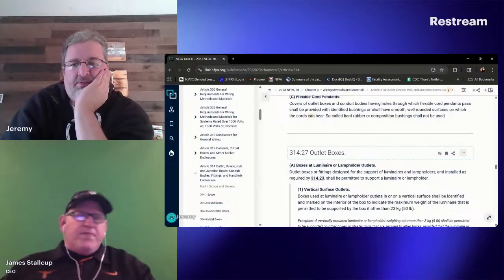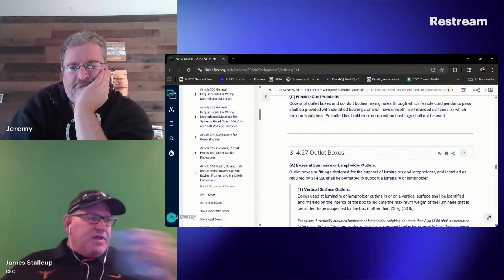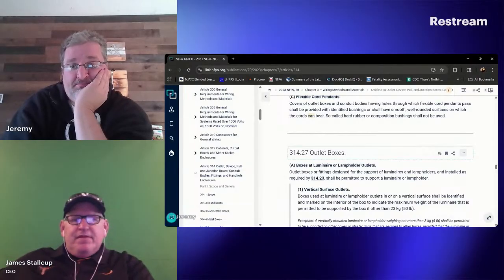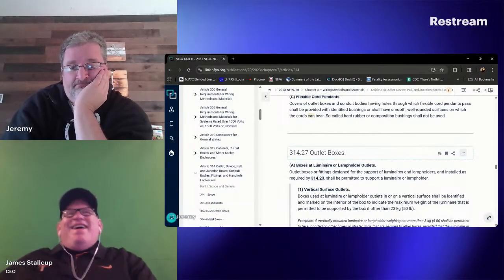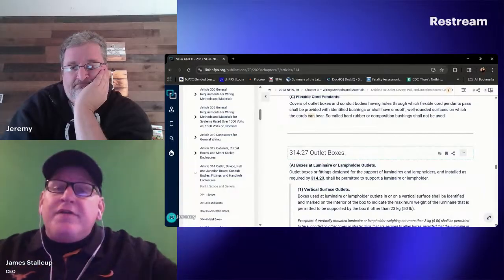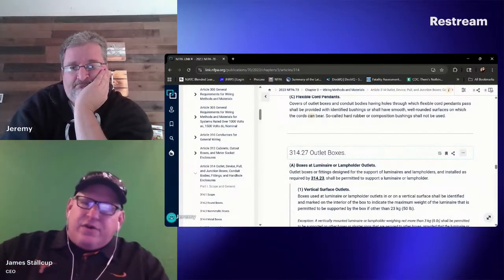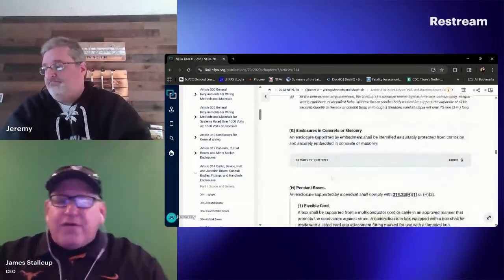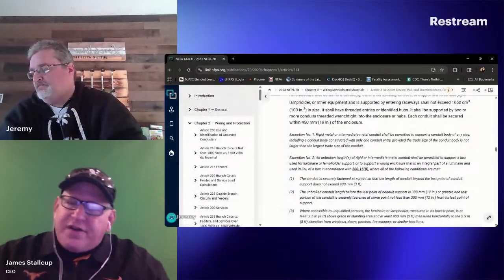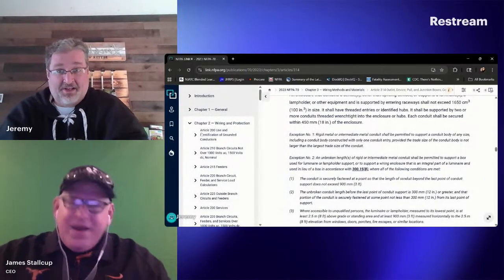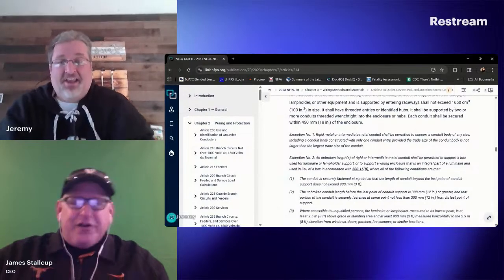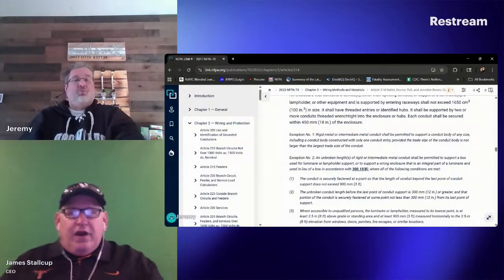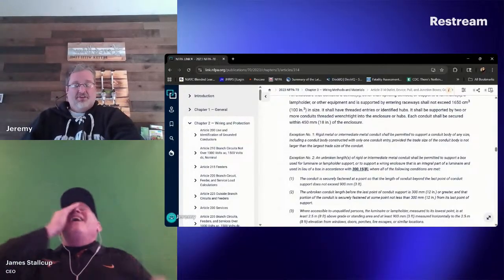Okay, so what size breaker are you using for all this? It could be a 20 amp. So you can put 14s on a 20 amp circuit? Have you never done electrical work? Have you ever been into a house and seen where they come over with number 12s and then they split off there with number 14s? Have you never seen this before? That's really a violation. Are you really serious? You can't do that. If you have a 20 amp circuit, you need number 12.